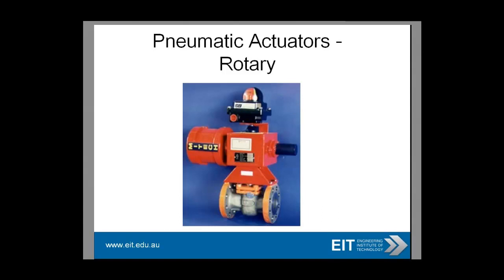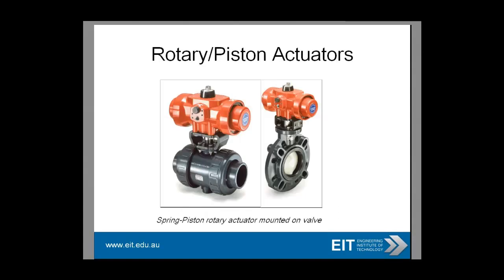You can have rotary actuators as single acting — air to open, spring to close, or air to close, spring to open — or as double acting. Double acting means you need to give it air to open it and air to close it. If you lose your air supply, it's going to fail in the last position it had. So your valve is going to dictate what the actuator will be. Just to clarify: the valve is the part marked in grey, and the actuator is the very large device at the top.